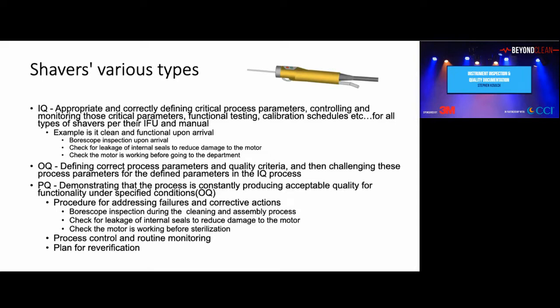But in most IFUs, it says clean it first before it can be used. So then you're going to clean it the way you're supposed to, and inspect it with that borescope. You might find there's rust or some things in there already that, if you didn't notice and document and take a picture, that might be acceptable. But if it comes through after it's been used and you say, is that blood or what is it? So you define the correct process parameters and the quality criteria, then challenge those process parameters for the defined parameters in the IQ process. And then you come to the PQ.